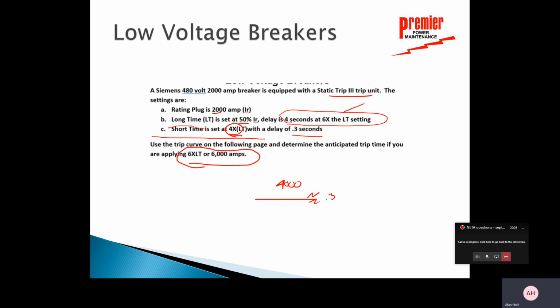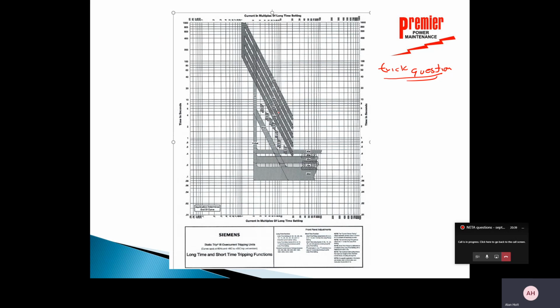If this statement wasn't even here, then I still wouldn't need to look at the curve because at 6 times it's set for 4 seconds. So we can look at the actual curve here and we can see that we got various areas, probably a little difficult for you to read, but right here is the 6 times window. And I believe that's the 4-second delay. So that would be the curve that you would typically look at for looking at long time pickup.